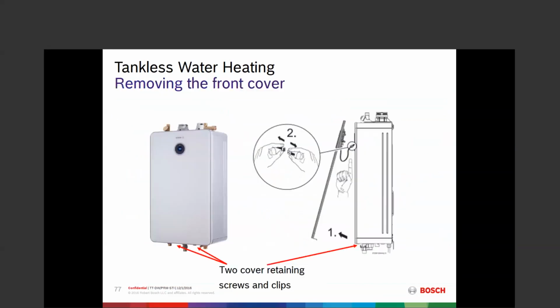Accessing inside of the cabinet, 2 screws at the bottom. The screws come off, the spring clips get released. The HMI is a quick disconnect here. It's not a Molex, it is just a quick disconnect plug here. And the unit will run with the cover off. It will run with the HMI disconnected. It will still run. So this truly is just a display for the ECU.